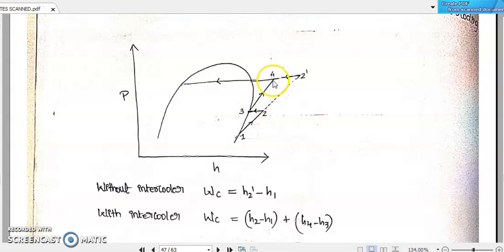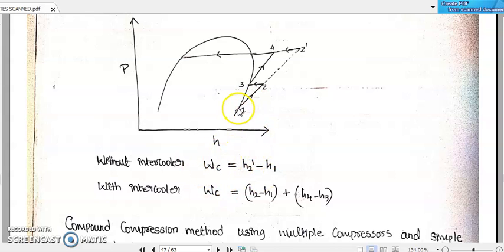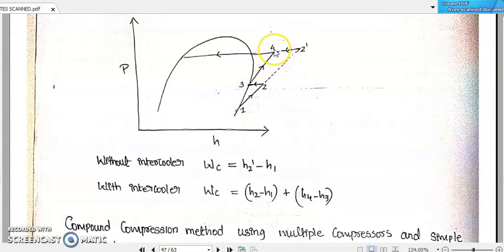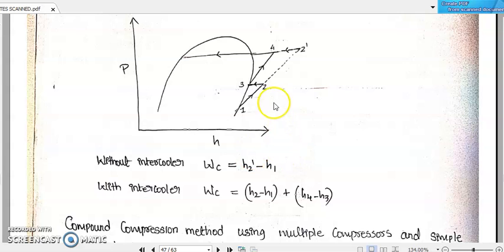After the first stage of compression, in the pressure-enthalpy diagram, line 1 to 2 represents compression by the first compressor. In a single-stage system, compression would continue all the way to point 2-dash, but that consumes a very large amount of compressor work. So we stop the first compressor at point 2. The refrigerant coming out at point 2 is in superheated vapor form, and it is cooled back to saturated vapor form at point 3 — this is the intercooling process. Then the second compressor takes the refrigerant from point 3 to point 4. Without the intercooler, compressor work is H2-dash minus H1. With the intercooler, it is (H2 − H1) + (H4 − H3), which is much less. By implementing intercooling between successive compression stages, we reduce total energy consumption and the total cost of running the refrigeration system.